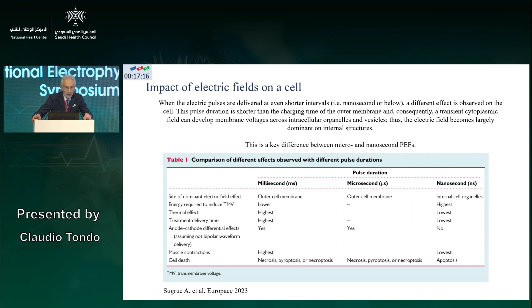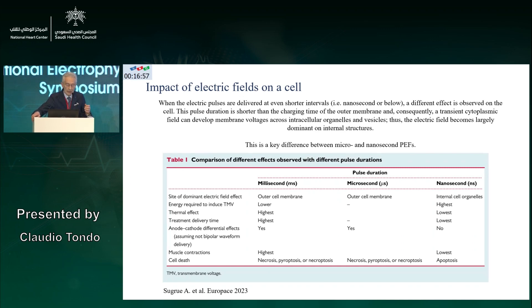If you apply nanosecond pulses, you can induce the lowest thermal effect. One of the principles of pulsed field ablation compared to other energy sources is its non-thermal effect. If you go to the nanosecond modality of application, you have immediate cell death through apoptosis.